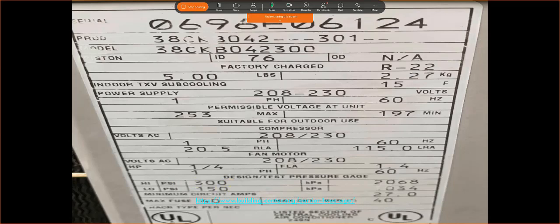So if I'm going to test the system pressure after I'm done making all my copper connections, I'm going to fill it with nitrogen to ensure that I don't have any leaks and we have a nice strong connection. I'm not going to exceed 300 psi. So that's it for this data plate.